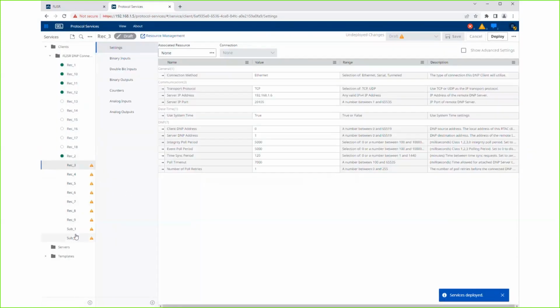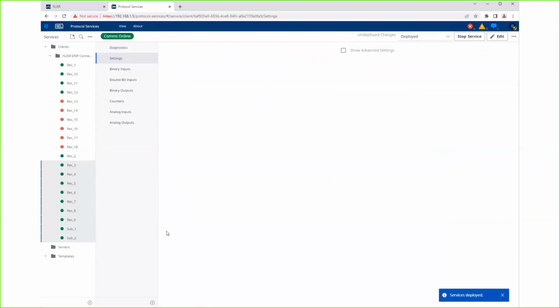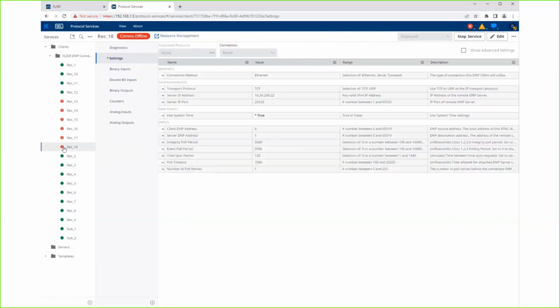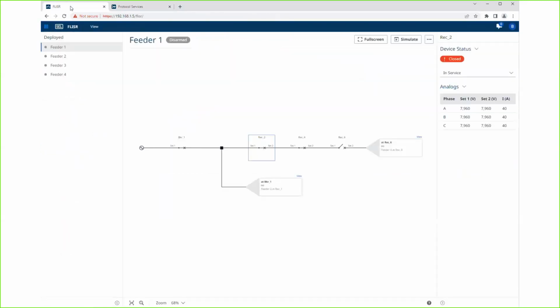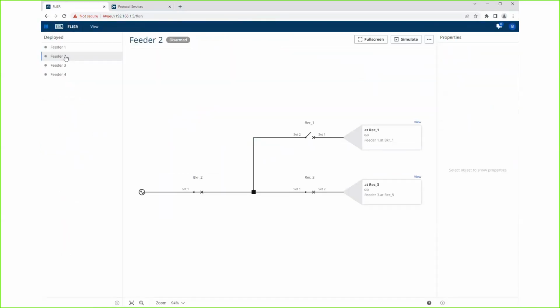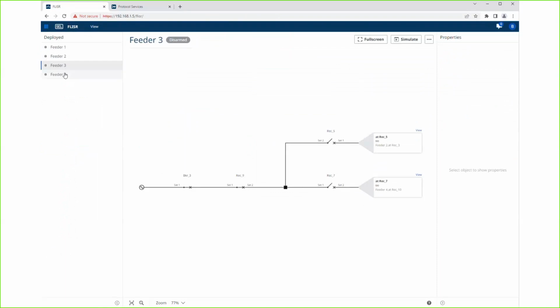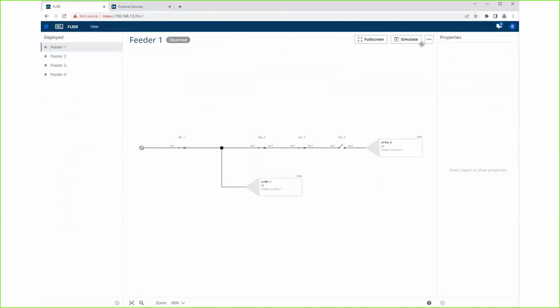So what you're going to see here, pretty interesting, you'll see a little green dot telling you that communications are good and online, show up next to all except recloser 13 through 18. The reason for that is because there is no DNP connection on the other end for these guys. There is no Rec 13 out in the field. And so you can see at a glance that there is a communications issue with those reclosers. Now, Rec 13 through 18, I didn't use in my FLISR configuration, so this doesn't worry me.